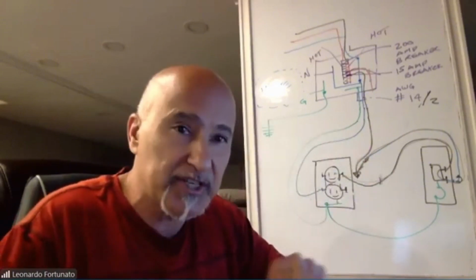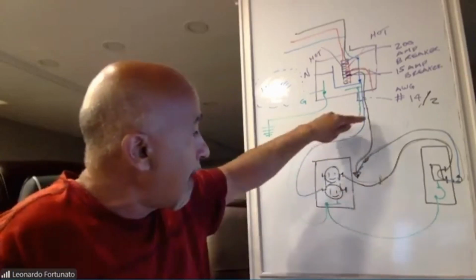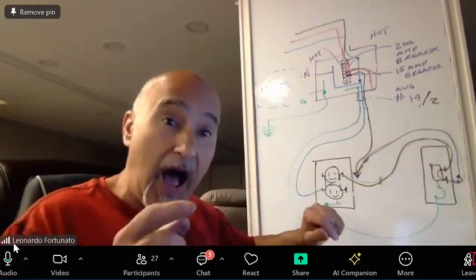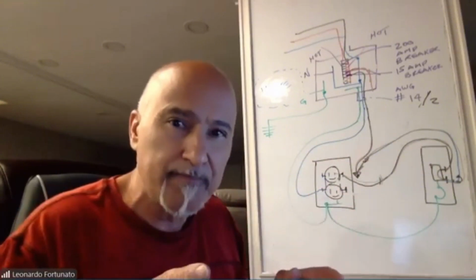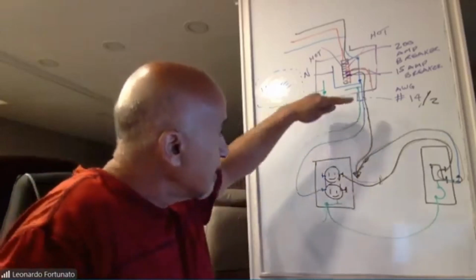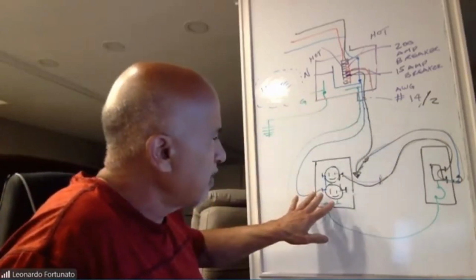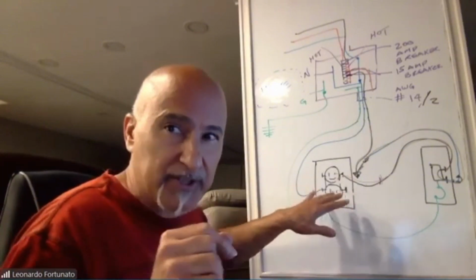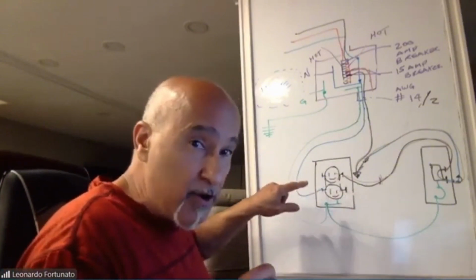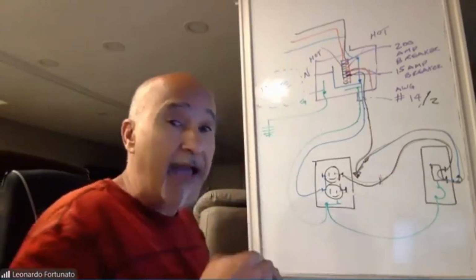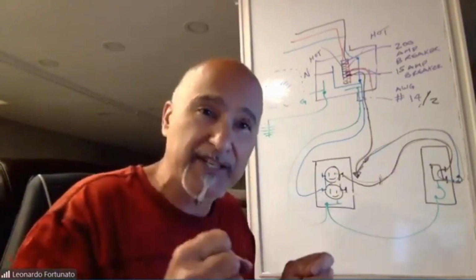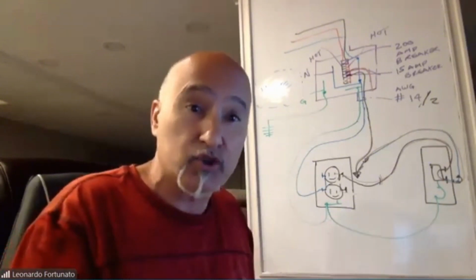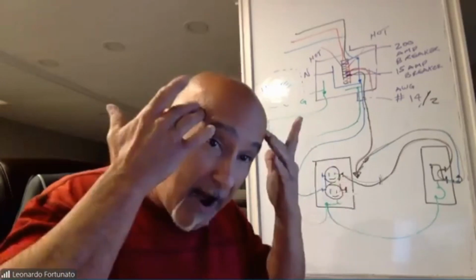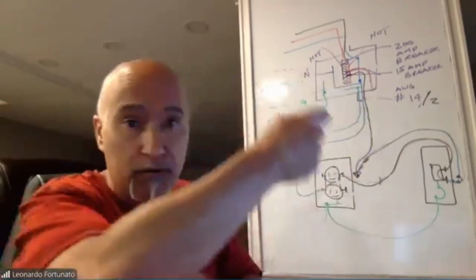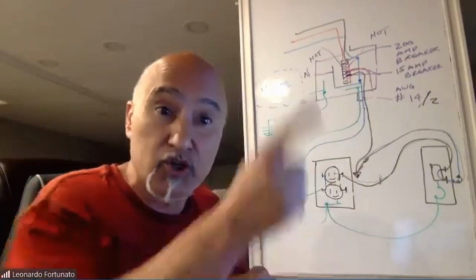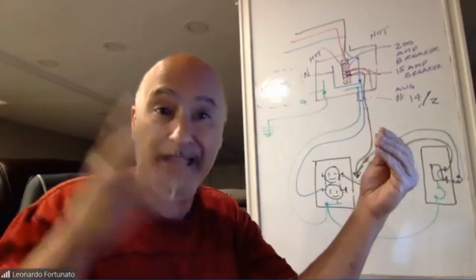But most of the time, when we see a wire nut, it's like when I'm running wire from this box to this box. When we use cable, look at the neutral. We'll be able to see this better when we start talking about switches. In a high-rise environment, when I use single-stranded or single-solid wire, if I'm smart, I can pull that wire through from box to box without cutting it, letting the neutral go from where it needs to go, from point A to point B.